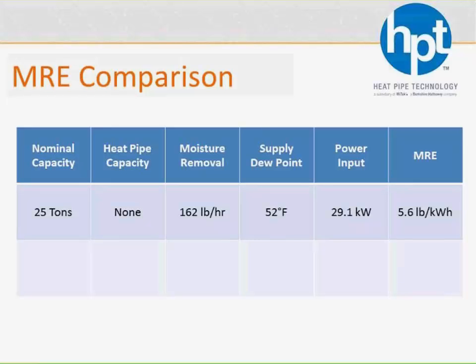But let's talk about how the heat pipe can be used to not just improve the EER, like we were just talking about, but now the MRE. I mean, EER, that's so 2015. Let's be serious. Let's talk about MRE. That's the future. So let's take that same 25-ton DOAS unit that didn't have a heat pipe in it. For it to get down to a 52-degree dew point, it had to remove about 162 pounds per hour of moisture. And to do so, it took about 29 kilowatts of power. So your MRE, again, is your moisture removal capacity divided by those kW. So you get an MRE of 5.6.